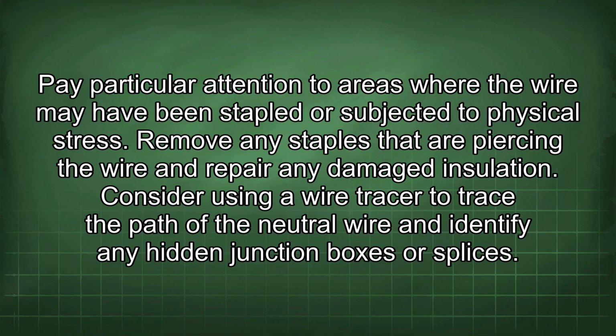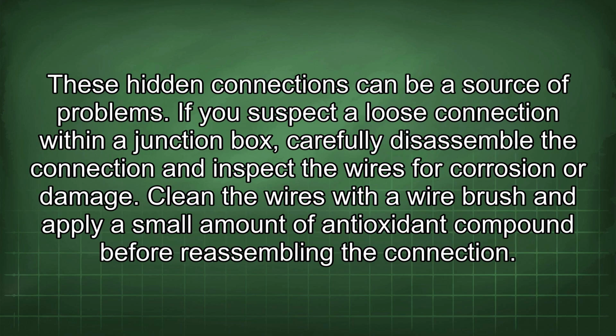Remove any staples that are piercing the wire and repair any damaged insulation. Consider using a wire tracer to trace the path of the neutral wire and identify any hidden junction boxes or splices. These hidden connections can be a source of problems.